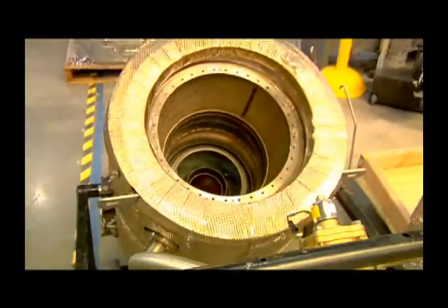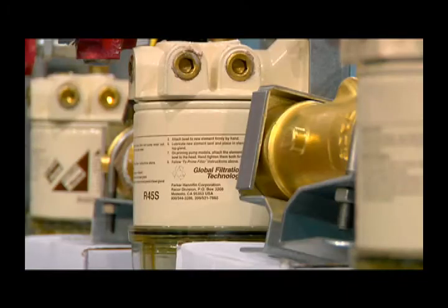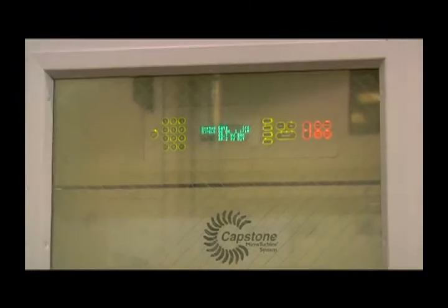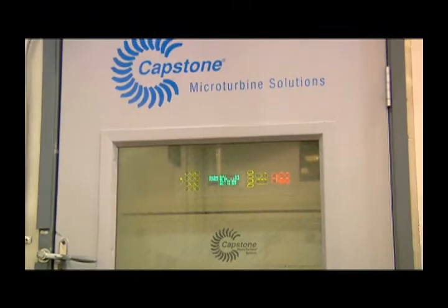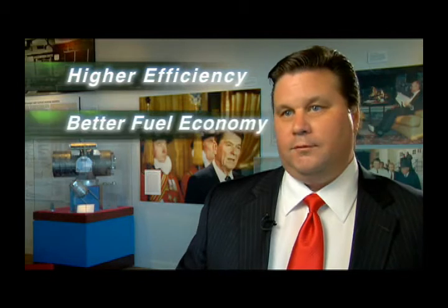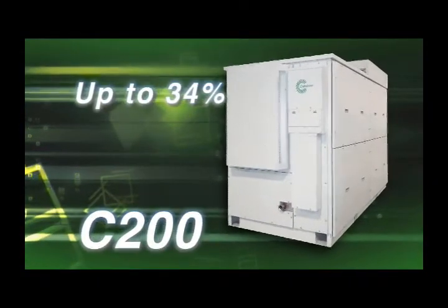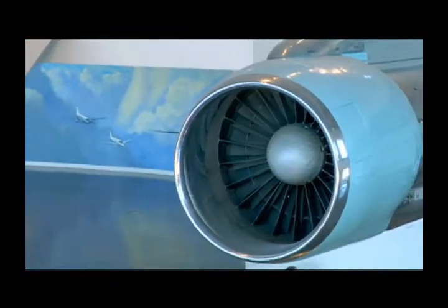In general, a microturbine is very similar to a commercial aircraft engine. We're taking fuel in for the combustion process in a lean combustion mixture combined with air. We ignite the fuel and provide heat to spin the turbine. What's a little different about our turbine, it has what's called a recuperator, an air-to-air heat exchanger. So we take the heat off the exhaust from the combustion process and preheat the incoming air. That provides higher efficiency to the turbine and better fuel economy. So overall, an unrecuperated turbine would be in the 15 to 20% fuel economy or efficiency range. We get up to over 34% with our C200 product with a recuperated version. So very similar to an aircraft turbine.